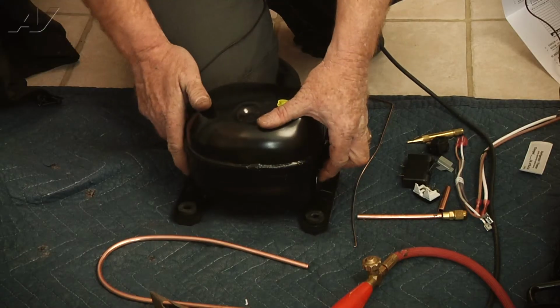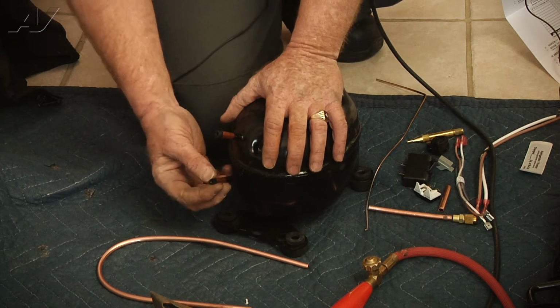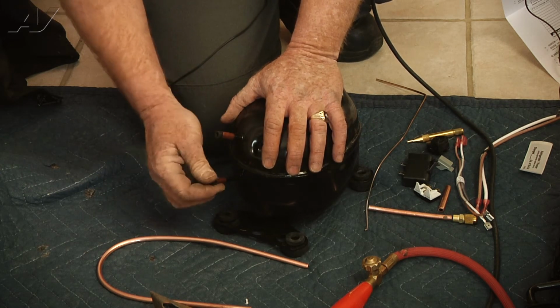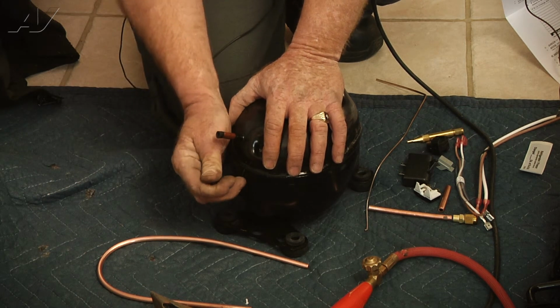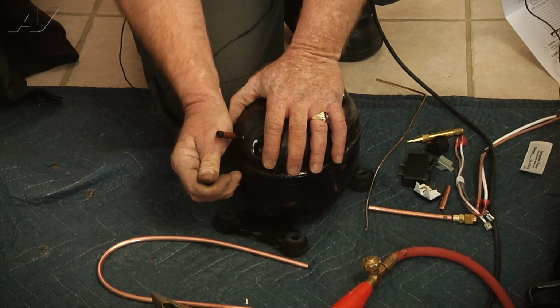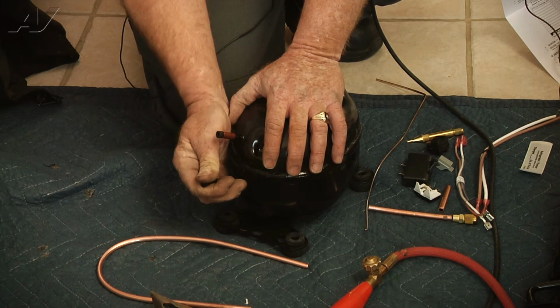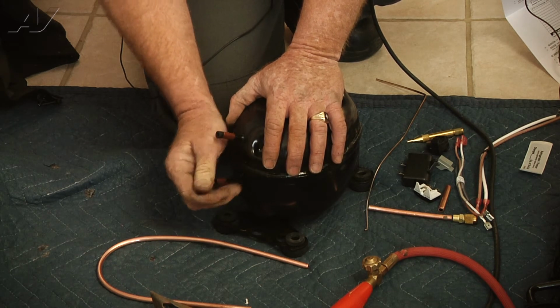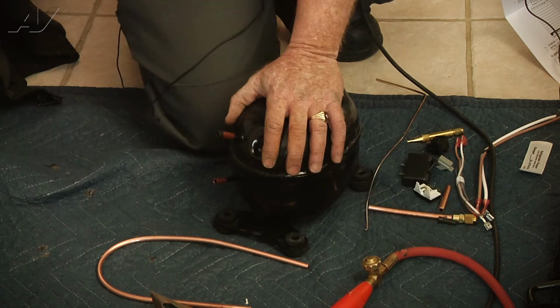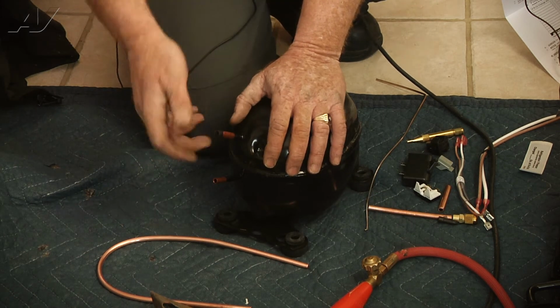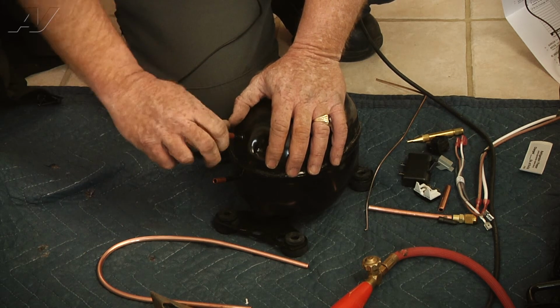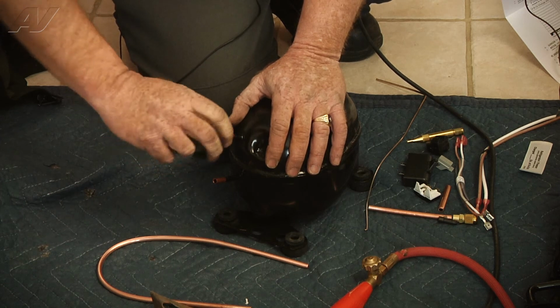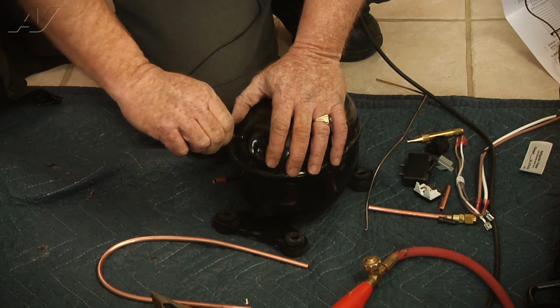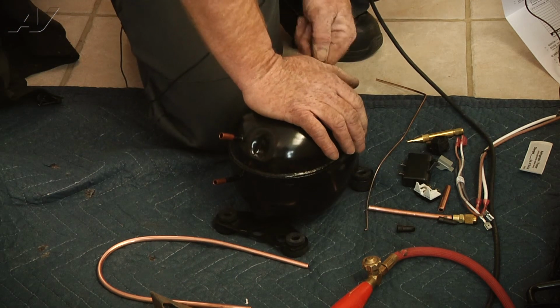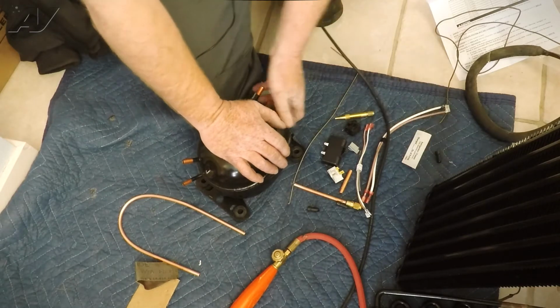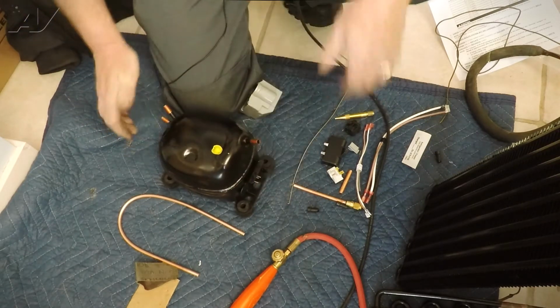Now I'm going to turn this so you can see. There are rubber stops that are inserted into the tubing, and we want to remove the high side first and just let that bleed off, because it is shipped with a little bit of nitrogen in it to keep it pressurized so that there's not any moisture in it, and you know there's no moisture in it as a technician when you pull that off and hear it hiss. And then we can take off the low side. And then the access valve port. And turn the compressor back where we had it.